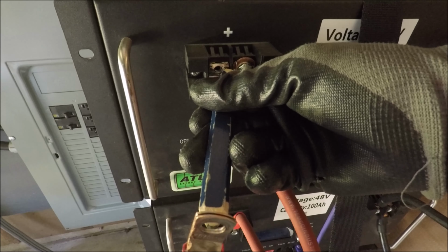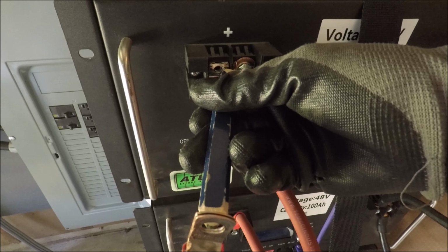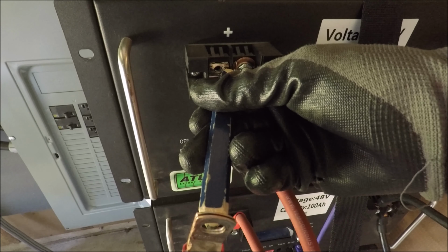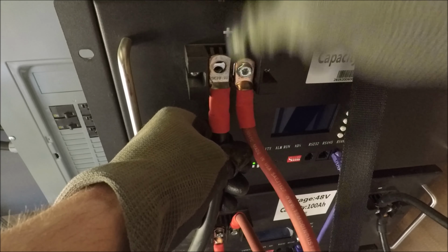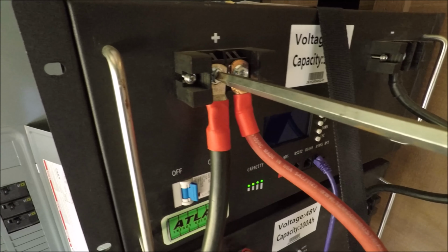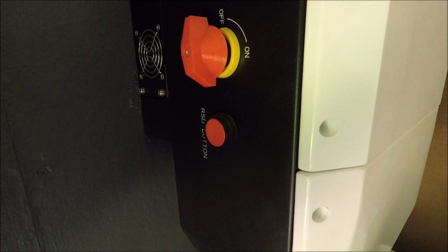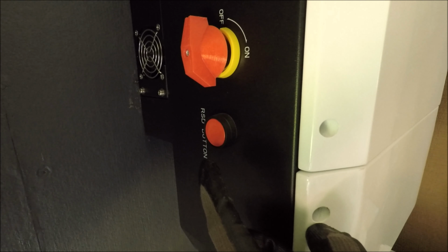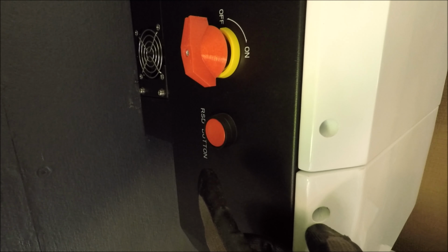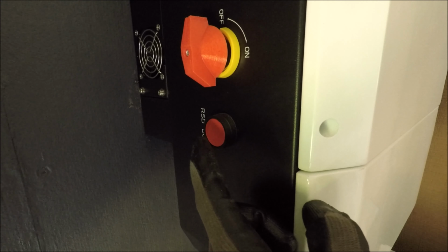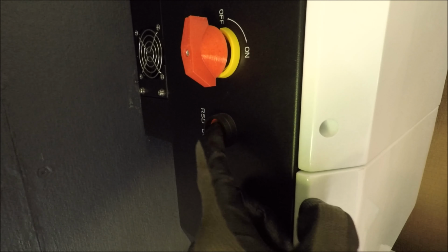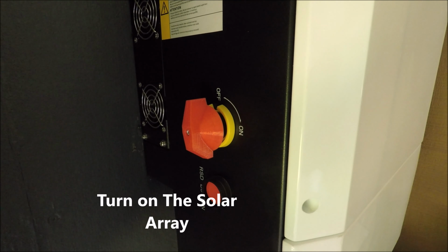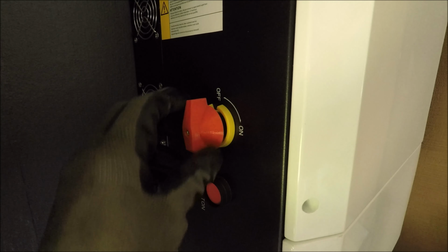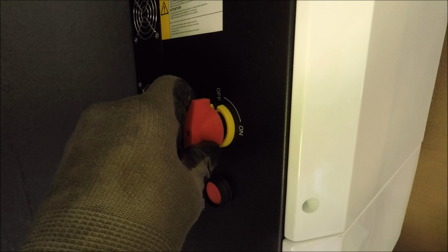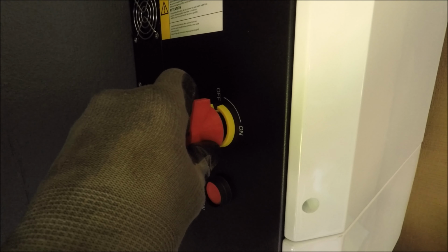Once the capacitors are fully charged, you want to move as quickly as you can to touch your battery cable to the terminal block. And there we go. The next step is to press the RSD button on the inverter. Some other inverters just may have a standard power button, but you press this button to activate the inverter. Next, you'll want to turn on the solar panel arrays, turning on the PV disconnect.